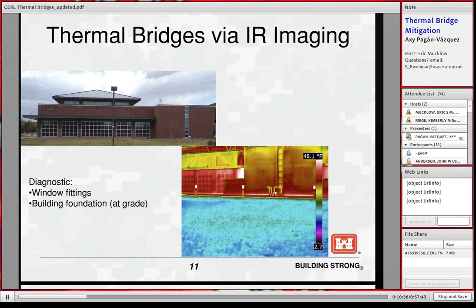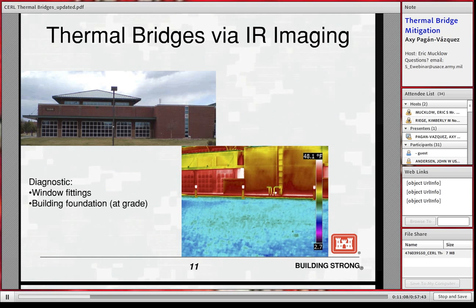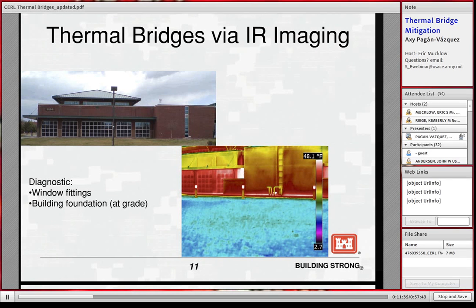Moving to a survey performed a couple of years ago: in the next few pictures, I'll show Army facilities where we used thermography or infrared imaging. The right infrared image shows high-temperature signatures at the grade level and the window frames. We need to clarify that infrared imaging is very useful to get a qualitative idea of what's happening within the building. However, although these images show nicely colored pictures, they can be somewhat deceiving — the camera captures emitted surface thermal radiation, whereas what we are trying to characterize is the effect of thermal conduction.